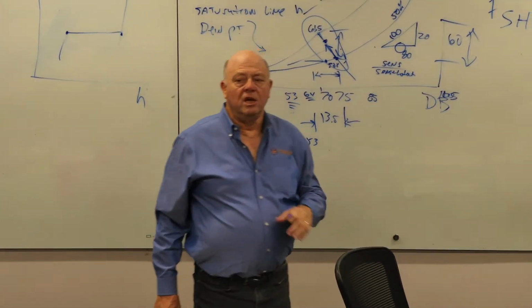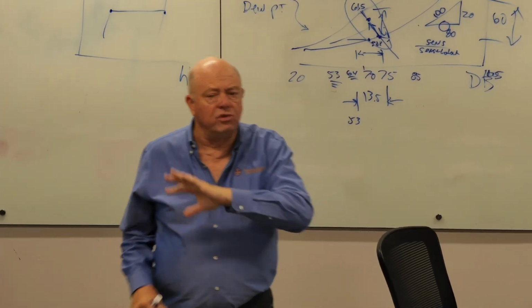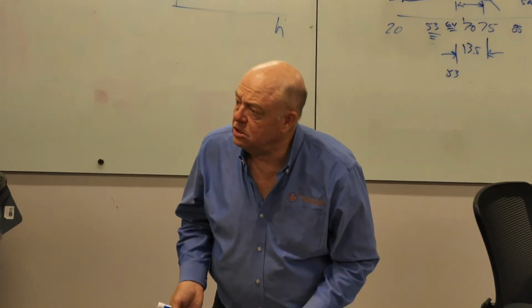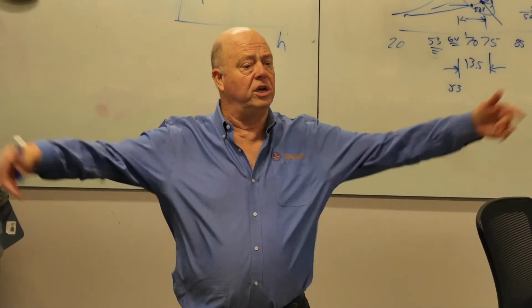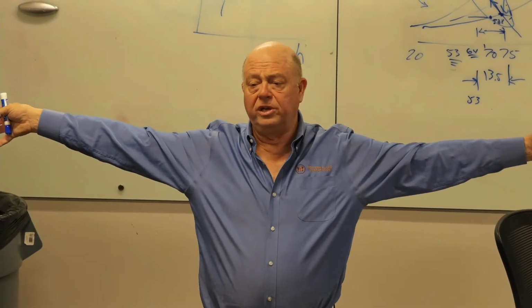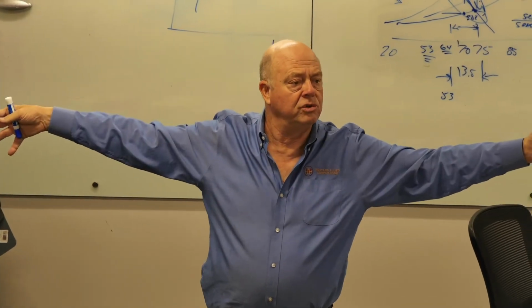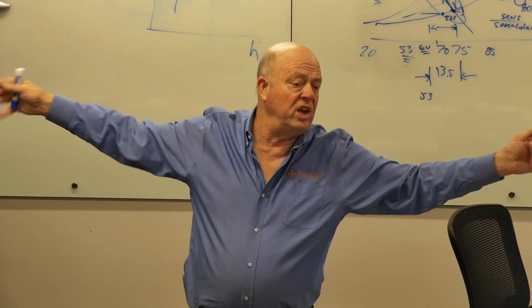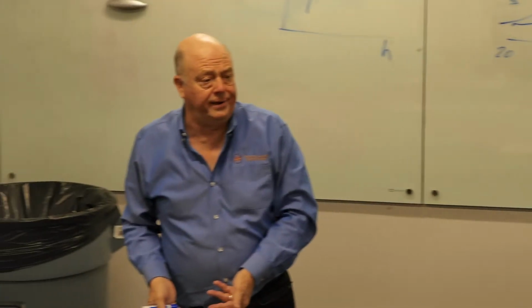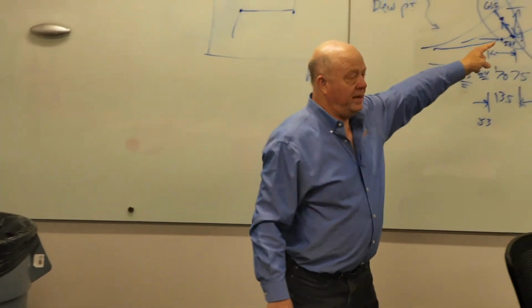Of the load. So if you started this whole process with a load calculation, and you said, I've got 100 tons in this big monster train station, one big room, 100 tons. And of that 100 tons, 80 is sensible and 20 is latent, and I got a 0.8.